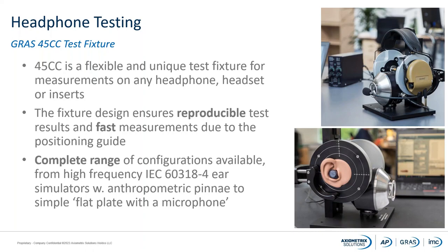We have a complete range of configurations available for this 45cc, going from high frequency IEC 60318 ear simulators with anthropometric pinna, and anthropometric pinna is a human-alike pinna where we also have a human-alike ear canal, to flat plates with microphone mounted. Let's have a closer look at the 45cc.